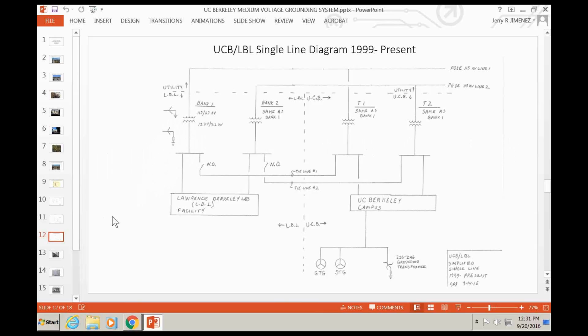What kind of cable, legacy cable, are you using? EPR, 15 kV? What kind of cable? Okay, so let's see. Another thing that was going on here around 1989, 1990, the campus was mostly 4160 distribution, and because of the growth, they decided to upgrade to 12 kV. So when they did that, they put in new cable, and the standard was EPR. And I'd say 98 to 99% of our cable is 12 kV or 15 kV EPR.